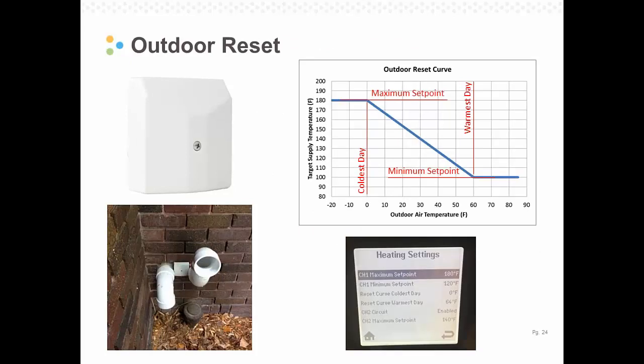The first thing, as Becky mentioned, is the outdoor reset. We saw some other research that pointed to this as a key component of getting boilers to operate well, and we saw some of that too. For anyone not familiar, in the upper left-hand corner of the screen is a picture of one of the outdoor temperature sensors that can be installed on the exterior of the home and wired back to the boiler. On the right side, you see the control algorithm and how it is set on the boiler itself. What the outdoor reset does is set the supply water temperature of the boiler, so it also essentially sets the capacity.